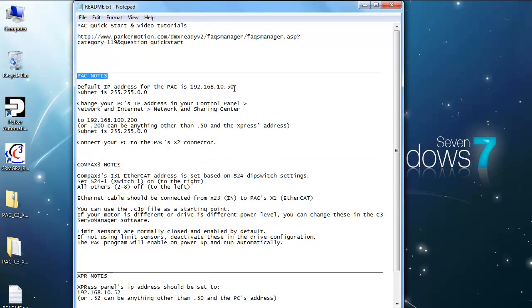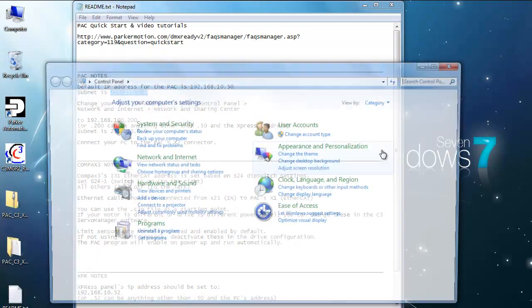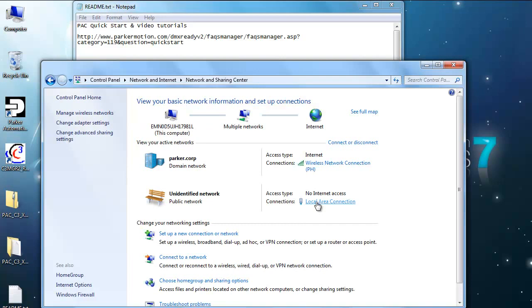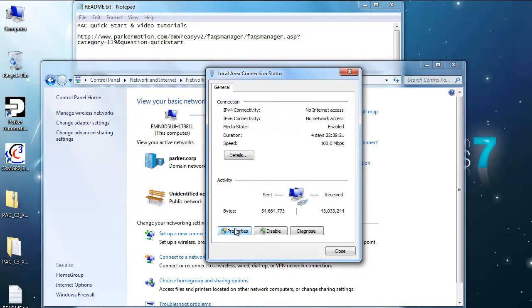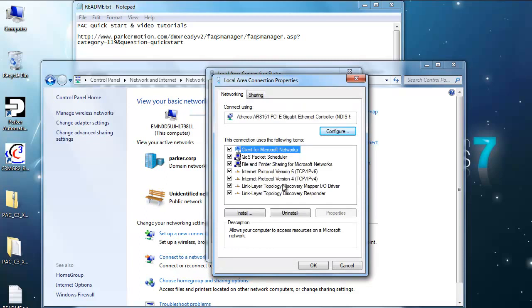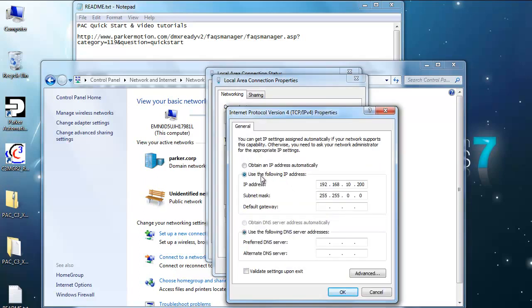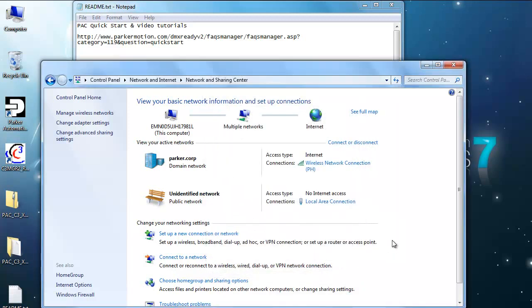Under the PAC notes, the default address for the PAC controller is 192.168.10.50, and the subnet is 255.255.0.0. Go into your control panel, network and internet settings, network and sharing center. Under your local area network if you're plugged in, go into properties, internet protocol version 4, IPv4, click on properties, and select use the following IP address. Set that to something other than .50 on the very end, with the same subnet. Go ahead and press OK, close, close, and close.